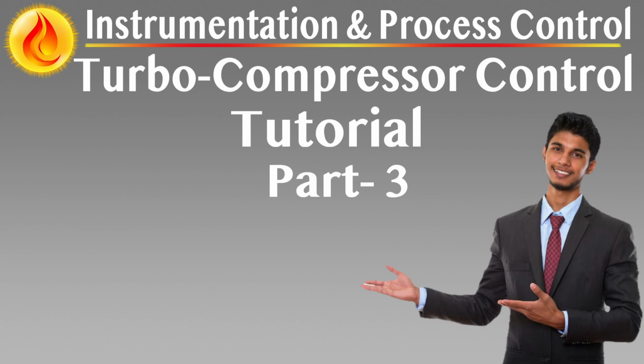Key load sharing control features: surge margin-based load distribution. Instead of balancing on speed or flow alone, the TCCS adjusts each compressor's load based on its distance to surge as calculated by the anti-surge controller. Speed reference coordination. The load sharing controller, located in the Common Control Panel, CCP, sends individual speed set points to each train's turbine governor. These set points are calculated to keep all compressors equally distant from their respective surge lines.